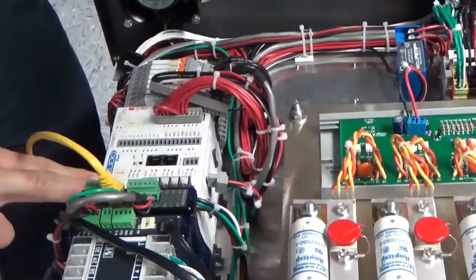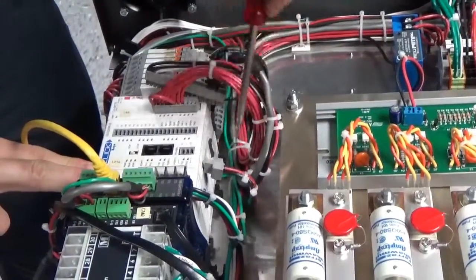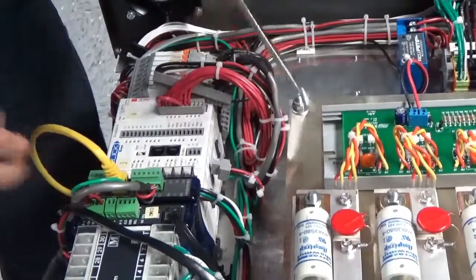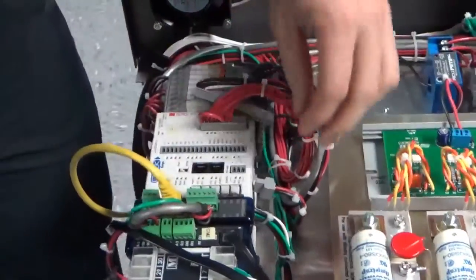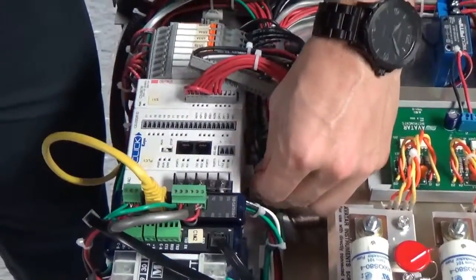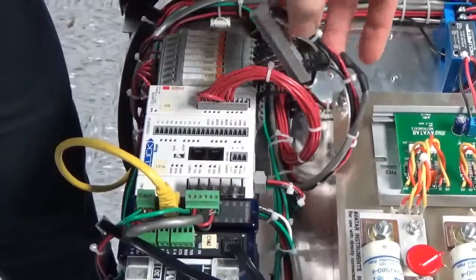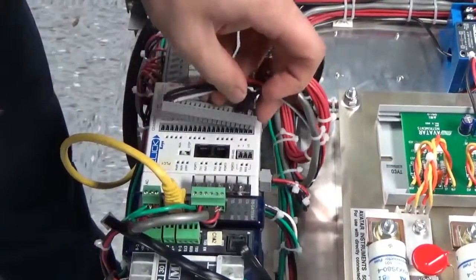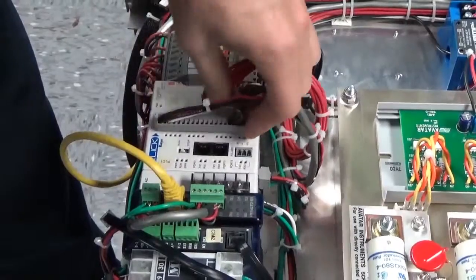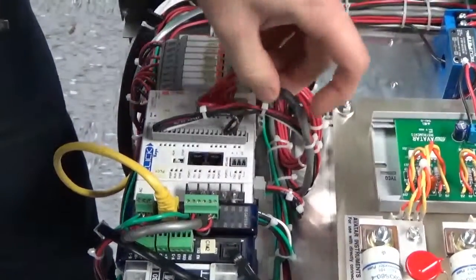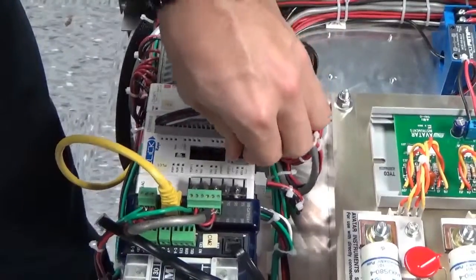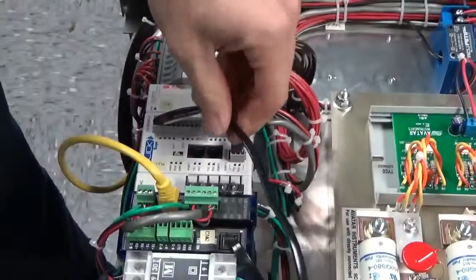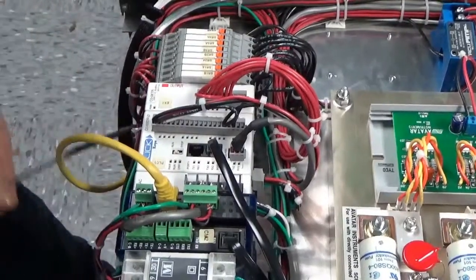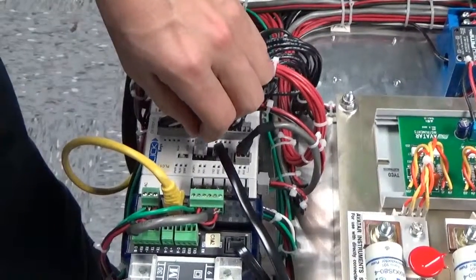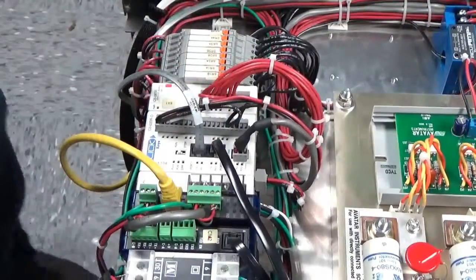Once I tilt in, take your flat screwdriver, press in on these locking tabs. That'll lock it to the DIN rail. There we go. And then from here, we're just going to plug our terminal strips back in. Here's our 24-volt supply, our input and output terminal block. It's pressed in, nice and firmly based in there. Next, this is our communication to the meter. This is our network communication here, and our communication to handheld controller. And there we have it, reinstalling our Click PLC in our Simplex load bank.